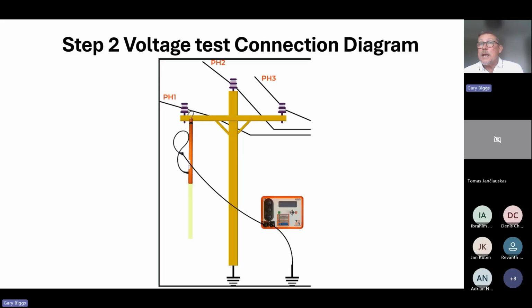and it gives the engineers the opportunity to go to site and find where these faults are. Invariably, when a system fault arises on an 11 kV system, the nature of that system is a long run. It's going to be a mile, and then anywhere up to 30 miles maybe. Therefore, it's not straightforward to find out where the fault is.